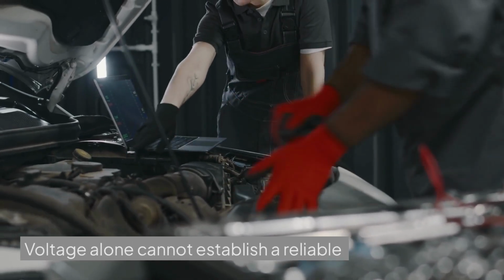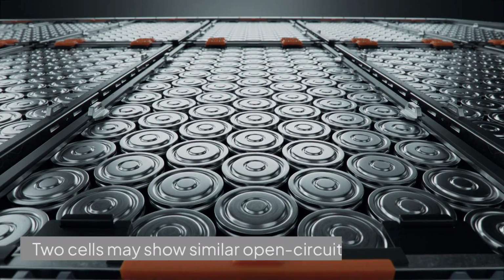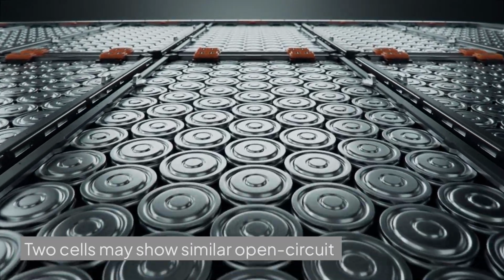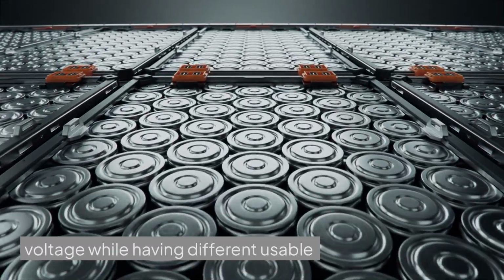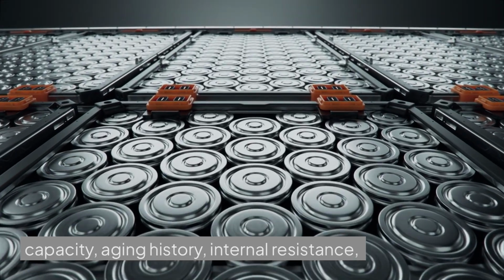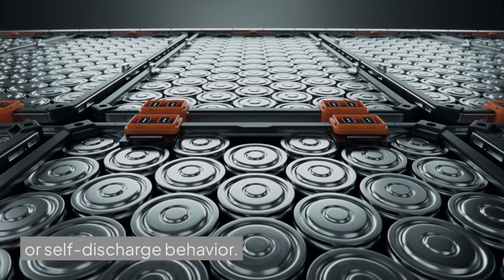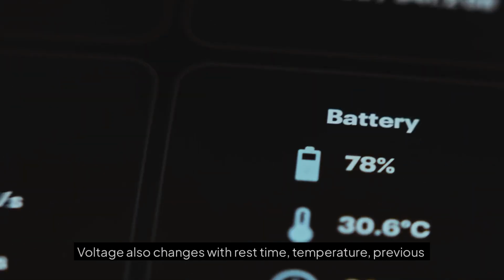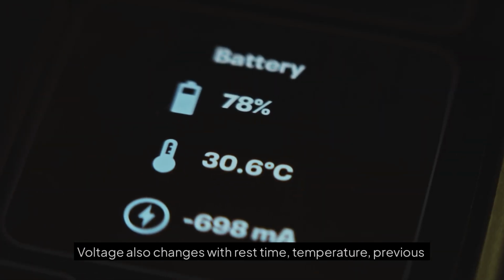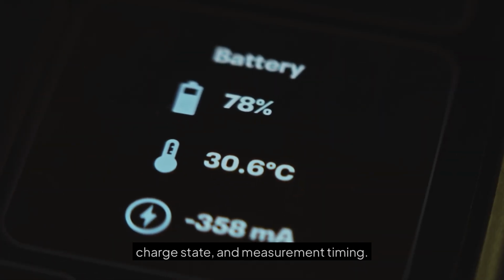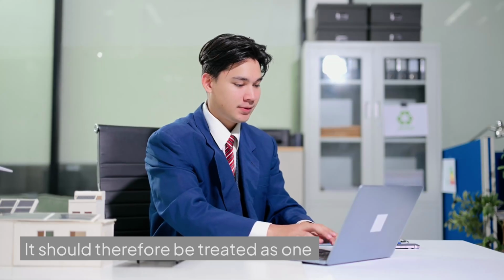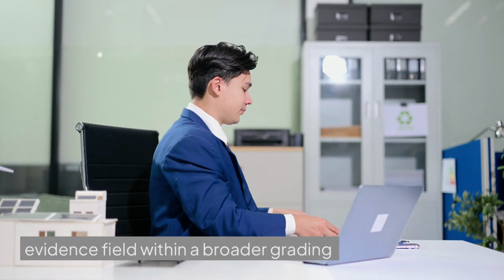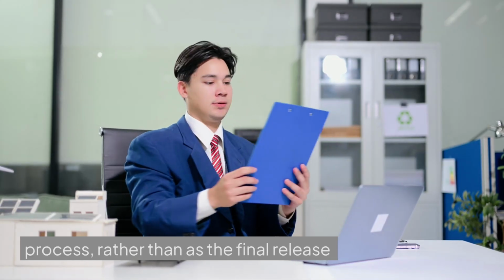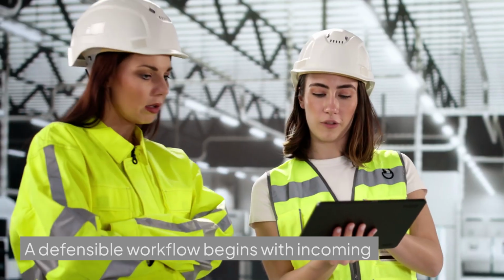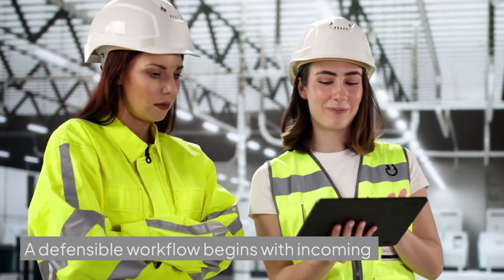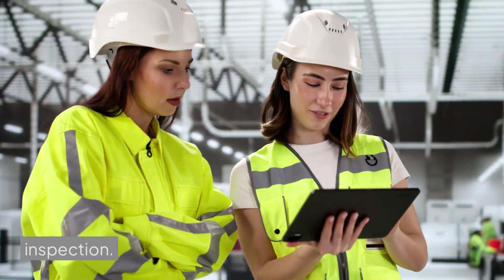Voltage alone cannot establish a reliable match. Two cells may show similar open-circuit voltage while having different usable capacity, aging history, internal resistance, or self-discharge behavior. Voltage also changes with rest time, temperature, previous charge state, and measurement timing. It should therefore be treated as one evidence field within a broader grading process, rather than as the final release criterion. A defensible workflow begins with incoming inspection.